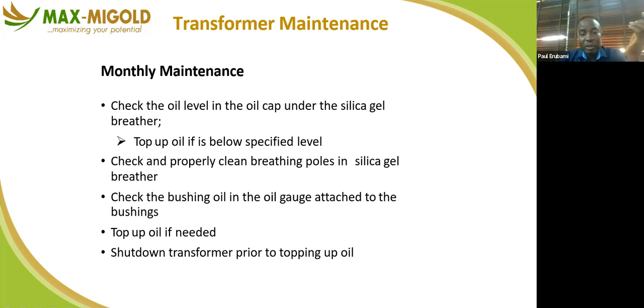So check the bushing oil in the oil gauge attached to the bushings. You top up oil if needed. You shut down the transformer prior to topping up oil. You don't operate the transformer or carry out maintenance on it while it's still live. So you have to ensure you put off the transformer before. In fact, for most electrical equipment, before you work on it, you have to ensure you switch it off in order to prevent electric shock and eventual death.